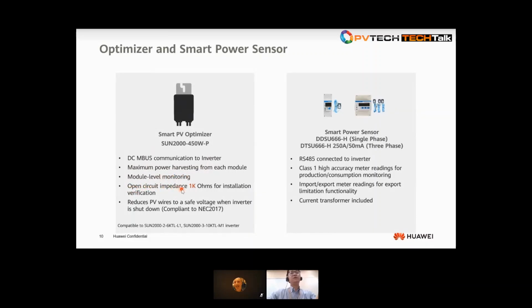But here, the open circuit impedance is used for the installation inspection, because before we connect the string to the inverter, we need to make sure the optimizers are connected correctly in the string. So how can we inspect or check that the optimizer is installed correctly? The indicator we can rely on is the open circuit impedance. For each optimizer we connect in a string, you will have 1000 ohms. So if you have 10 optimizers in that string, you'll get 10,000 ohms. So the installer can inspect before they connect this string to the inverter.